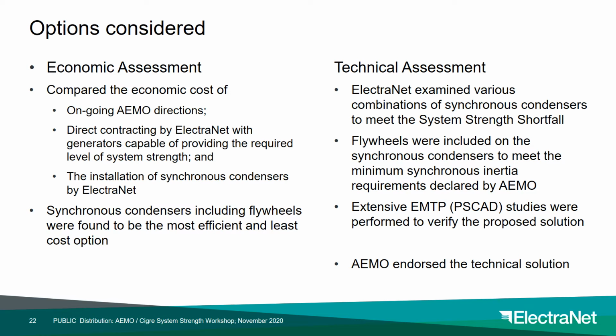A key preference was placed on well-established and reliable technical options in addressing the gap, and therefore various combinations of synchronous condensers were examined as the network solution. With the declaration of the inertia shortfall, flywheels were also included on the synchronous condensers. The economic assessment compared the ongoing cost of AEMO directions against the cost of Electranet commercially contracting with generators to provide the system strength services required, and comparing this against the installation of synchronous condensers by Electranet as a network augmentation. The addition of synchronous condensers, including flywheels, was found to be the most efficient and least cost option compared to either directions or contracting of generation by Electranet.